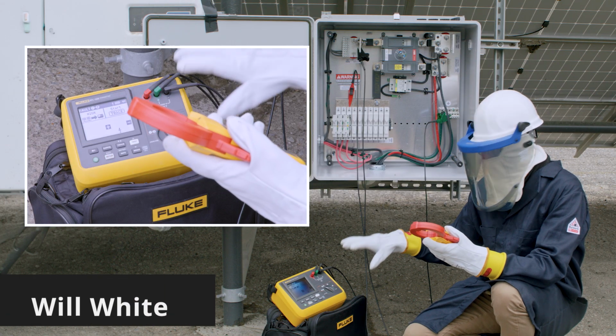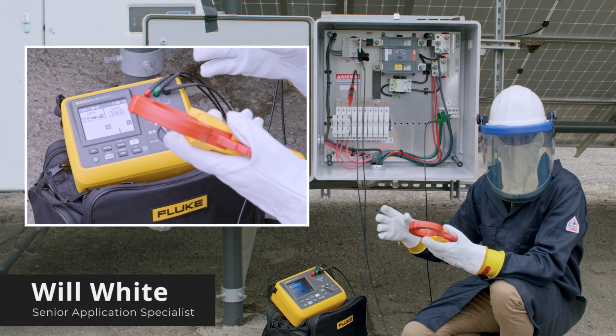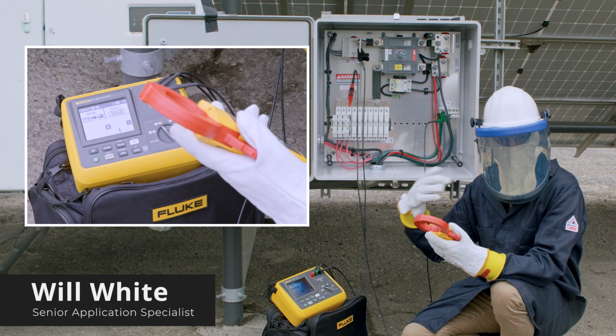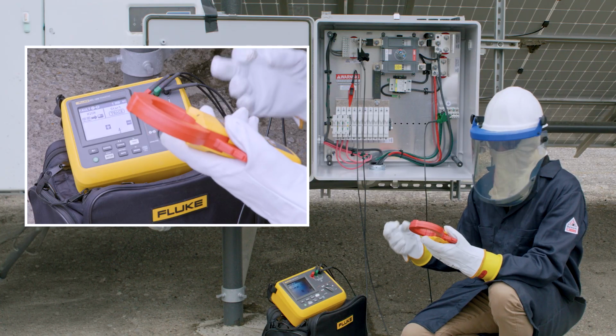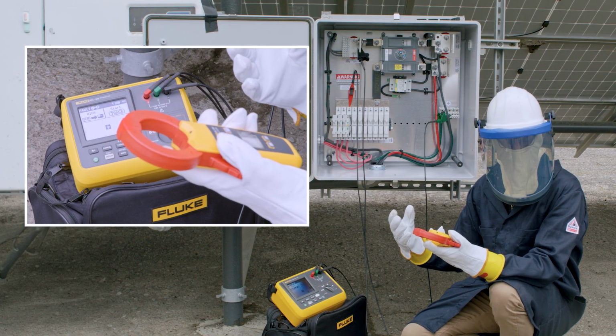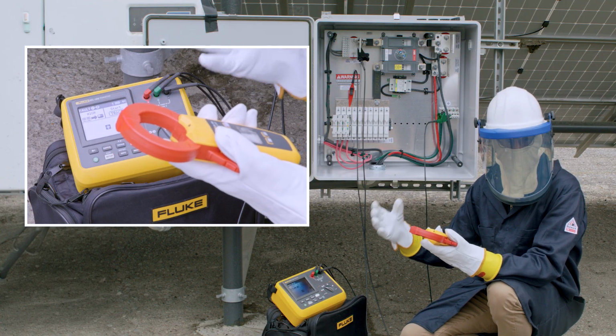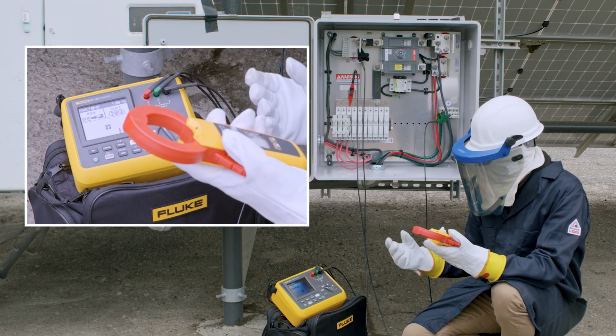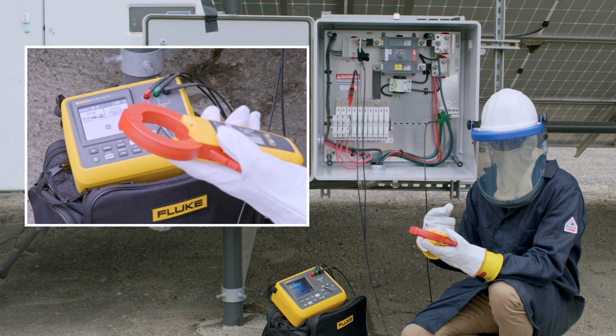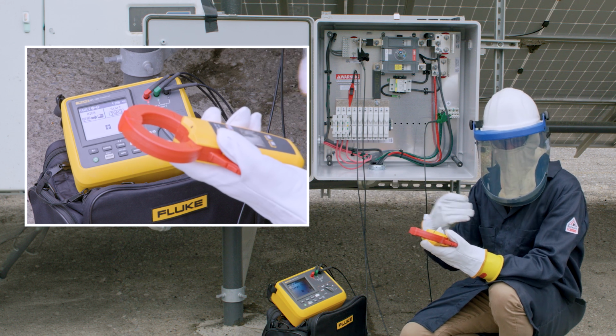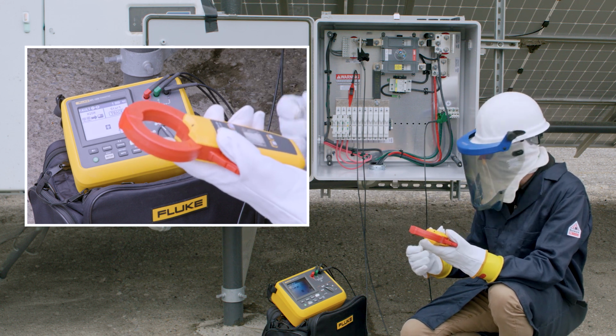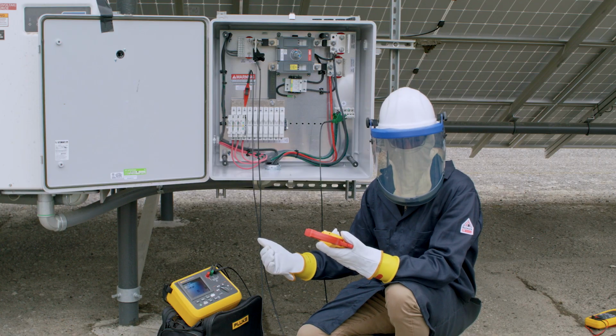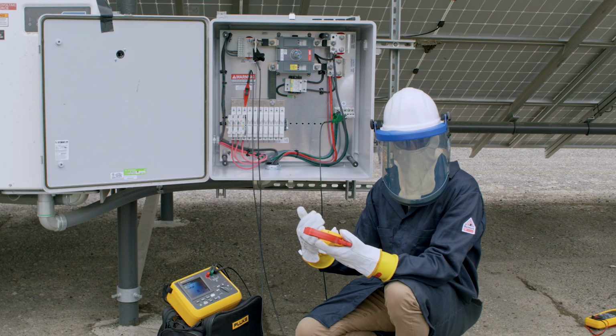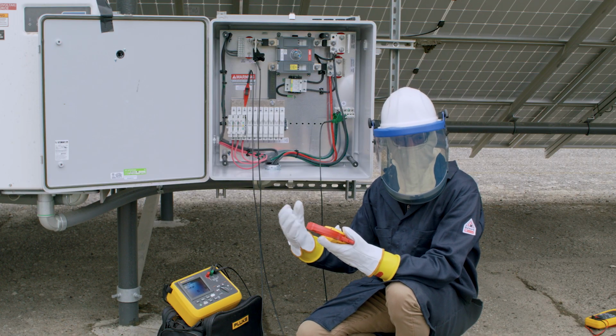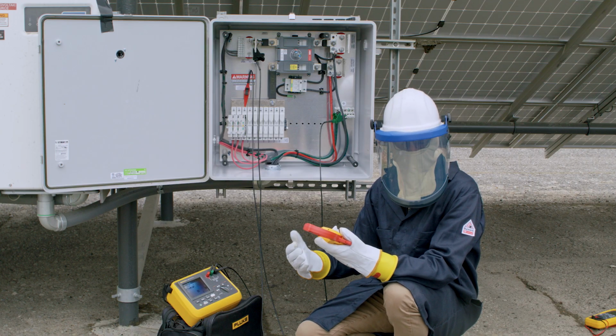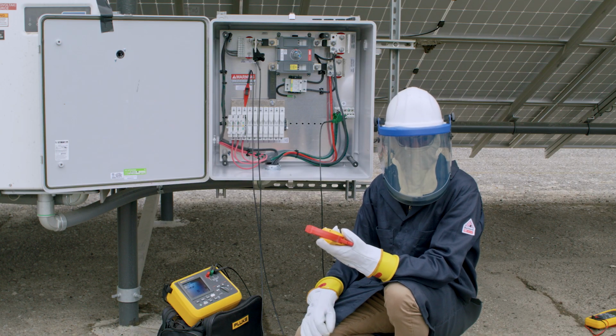The GFL-1500 array mode has two options, high and low, and that's the amount of current that's being sent through the signal. In most cases, especially when you have a low resistance solid ground fault, high mode is going to be the optimal option. In some cases, when you have a high resistance ground fault, that's too much current to pass through the ground fault. So using the low option will still allow it to source the signal from the array, and it might be easier for you to trace in those situations where you have a high resistance ground fault.